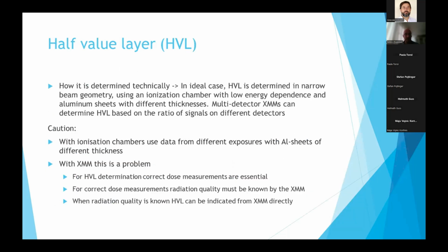The next quantity is half value layer. So you know that you can use some detector that has low energy dependence, such as an ionization chamber. And then you can measure air kerma without any filters, and then you can just keep adding aluminum filters until air kerma drops to 50% of the initial value. And in that way, you can measure half value layer. But of course, this procedure is complicated and takes a long time, which is usually not available in clinics. XMMs use several detectors that they have behind different filters to calculate HVL from one single exposure.